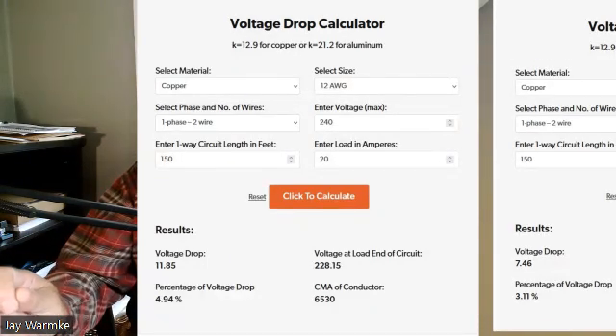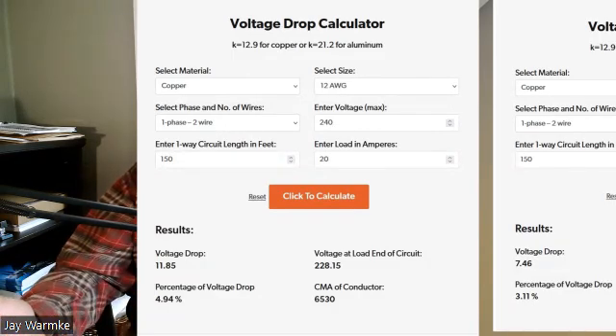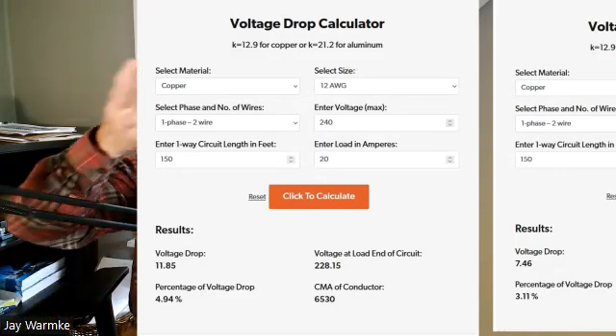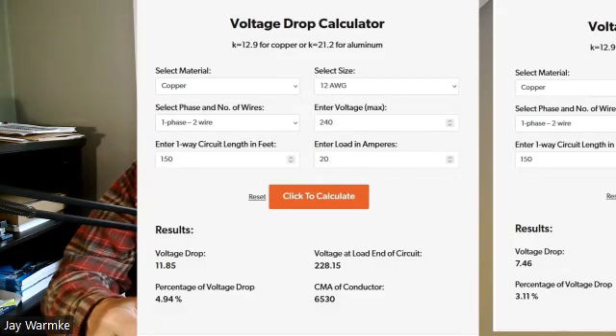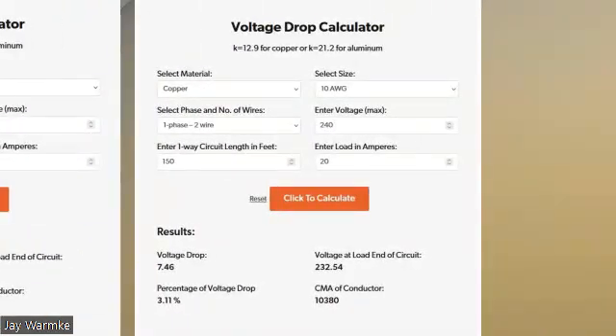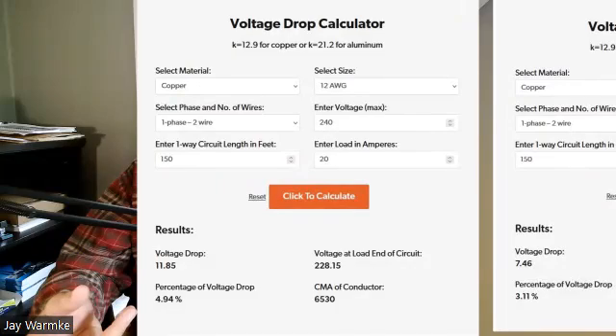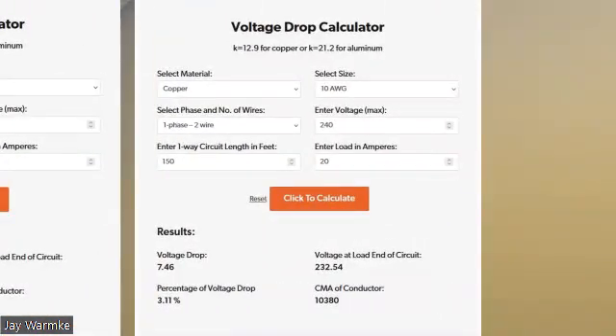And that's going to be 4.94% of power. That's my power loss due to voltage drop. Pretty significant, but it's 12 gauge cable. If I decide to upgrade and put in 10 gauge cable on this same run, everything being held the same except for the size of the cable, now I've lost 7.46 volts. Now it's only 3%, 3.11 versus the 4.94%. So that's an example there of just how impactful changing the size of your wire is.